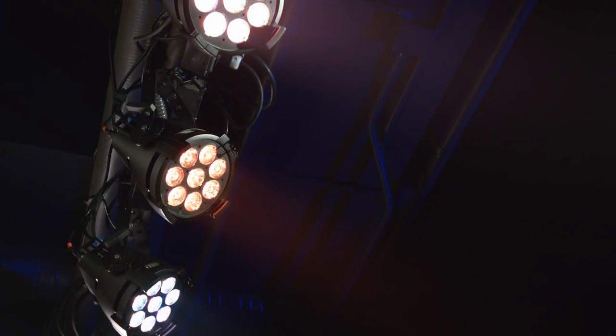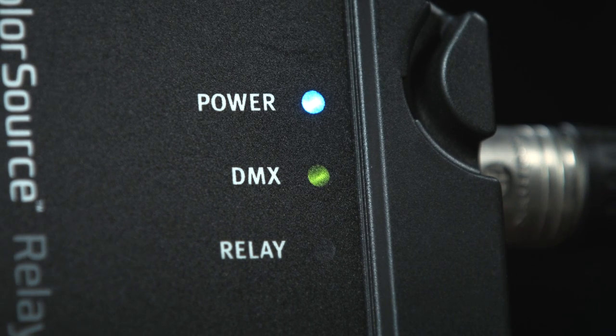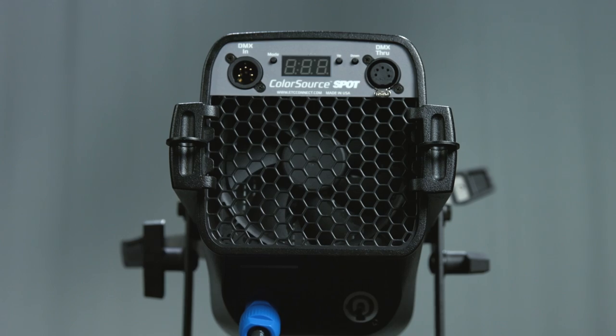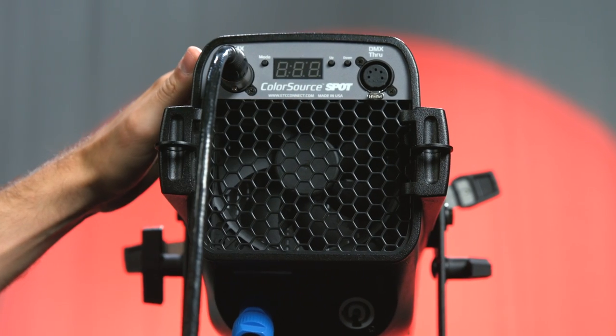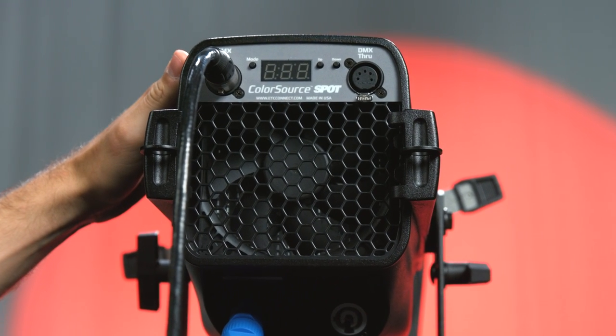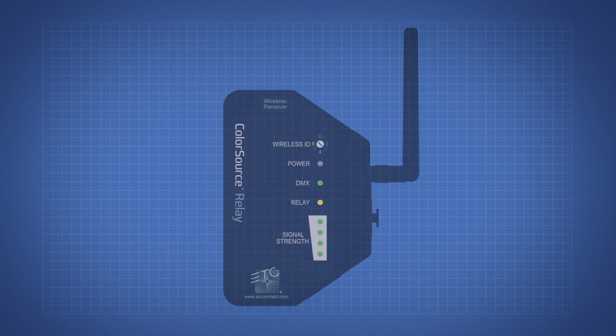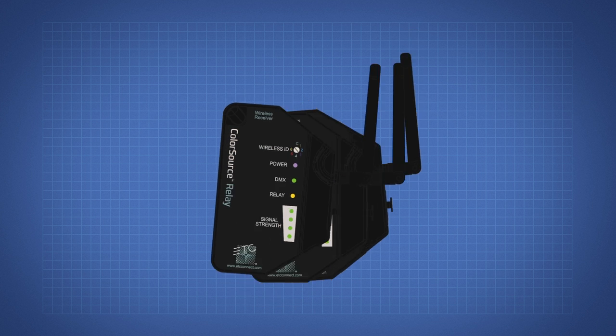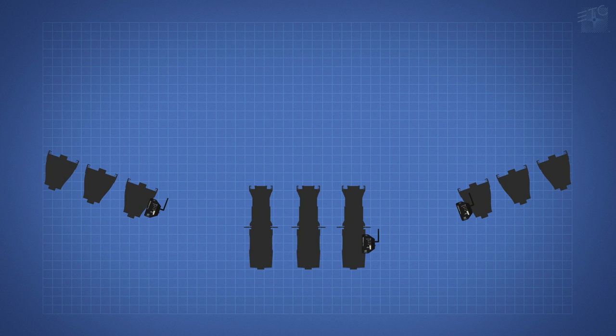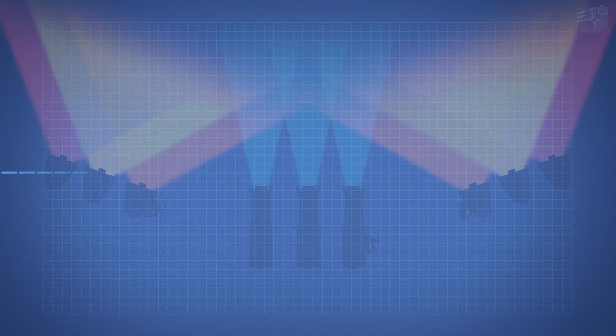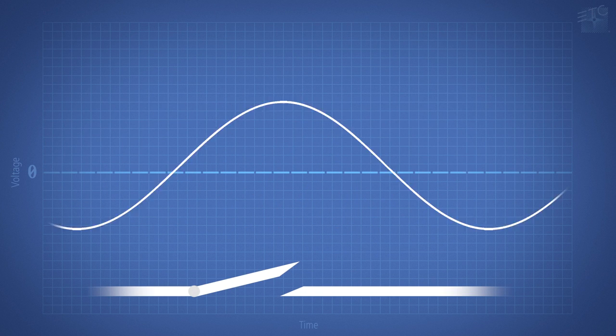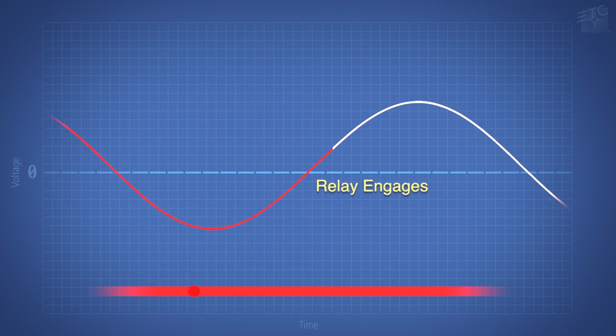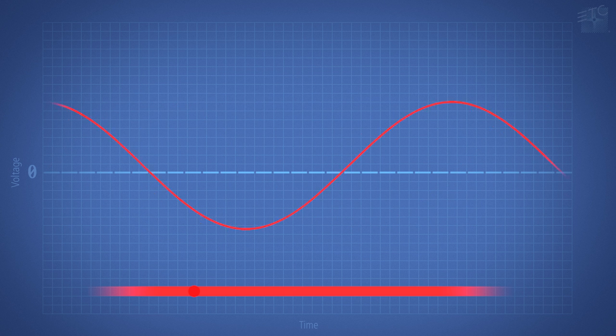By default, when the wireless relay receives a DMX signal, the relay automatically switches power on and DMX is transmitted to the connected fixtures. To minimize inrush current and avoid nuisance tripping, the ColorSource Relay uses a randomized delay routine and switches power at the zero cross point in the sine wave. The system is powered and controlled within seconds.